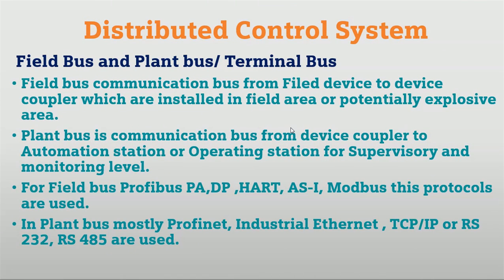Field bus is the communication bus from field devices to the device coupler, installed in the field area or potentially explosive area. Plant bus is the communication bus from the device coupler to the automation station or operating station for supervisory monitoring level. In the field bus, protocols like Profibus PA and DP are used since they can operate in potentially explosive areas. In the plant bus, high-speed communication like Profinet or industrial Ethernet TCP/IP is used. Based on application and environment zone, we select the appropriate communication protocols.